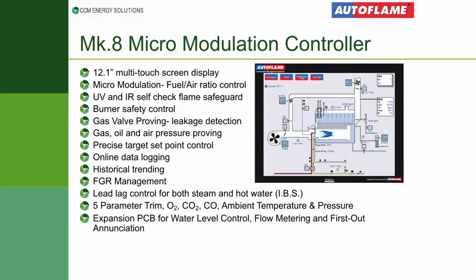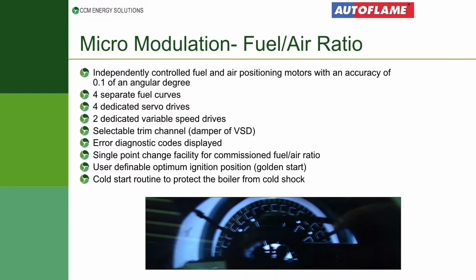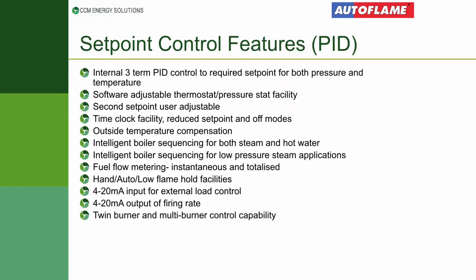The next few slides I will go through quickly. You can read them. It just kind of covers a lot of what I've discussed already. I did leave them in. But they do show that there's about 400 different settings within that controller to make sure it works for every application. If you have a manufacturing site, and they close operations at midday on Saturday and start up at 6 a.m. on Monday, most of those sites, that boiler keeps running. There's absolutely no point. This has an automatic start function within it to bring it on at 4 a.m. on Monday.